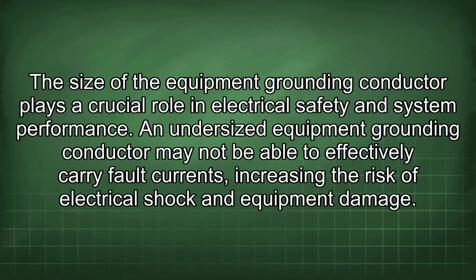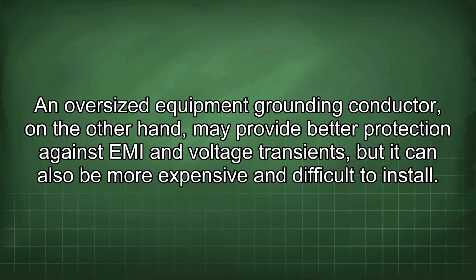The size of the equipment grounding conductor plays a crucial role in electrical safety and system performance. An undersized equipment grounding conductor may not be able to effectively carry fault currents, increasing the risk of electrical shock and equipment damage. An oversized equipment grounding conductor, on the other hand, may provide better protection against EMI and voltage transients, but it can also be more expensive and difficult to install.